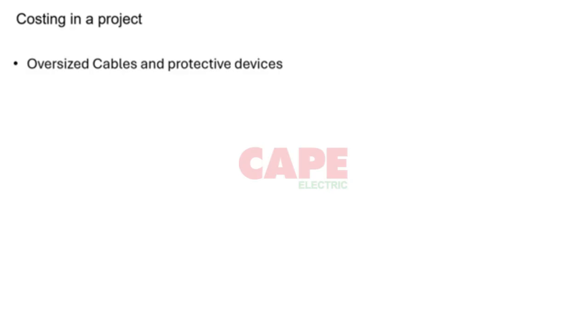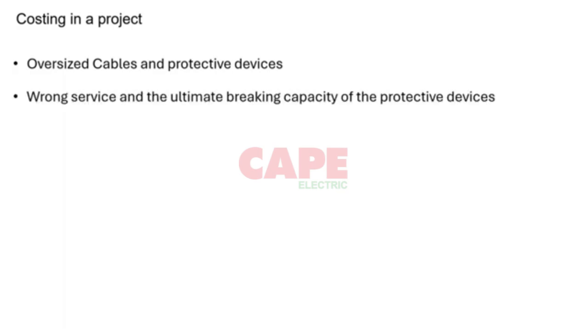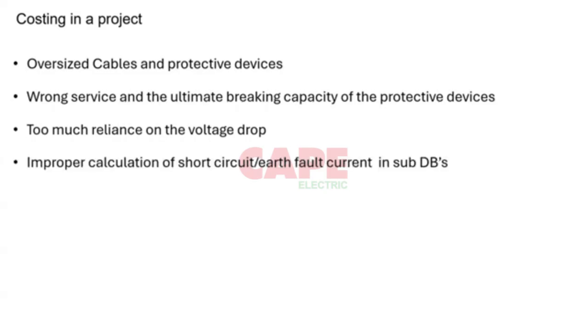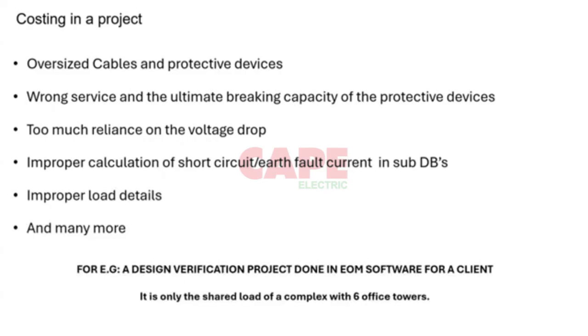It is going to affect the costing of the project, obviously. So most of the cables and protective devices are going to be complicated. You are going to have wrong service and ultimate breaking capacity of the protective devices. You are going to rely too much on the voltage drop. You are going to have improper calculation of fault and short circuit current in each DB. And you are going to have improper load details and many more. So for this, I'll just show you this example.